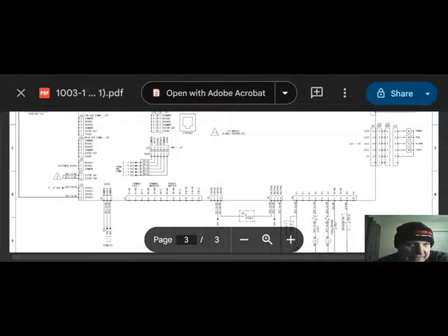How you tie this in is going to depend greatly on how you're integrating this. Is this something where you have a system that looks for an input and then alarms when that input goes away, or does it look for an input not to be there and then alarms when that input comes? If it's a light that's on, and if you have this rigged up to a light or something, is that going to be looking for power on fault? So that's what you've got to figure out beforehand, is knowing exactly what you're tying into with this and what kind of signal it's going to be looking for.